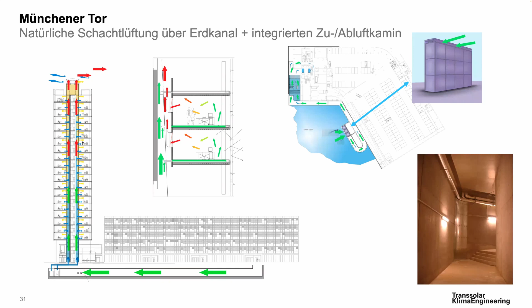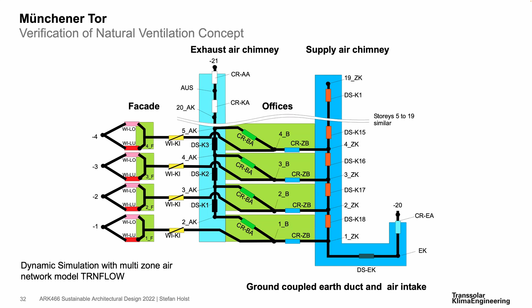And on the lower right, you see the earth duct. This is a 130-meter long channel in the ground, 3 meters by 5 meters, to use natural cooling and natural preheating to provide air. The question of the client was, will that work? Only natural forces. So we had to run a couple of complex simulations for shafts and offices and facades to show that it works. And then the mechanical engineers came in and said, but we need an exhaust air system on top of the roof with filters and all of that, like a big box.